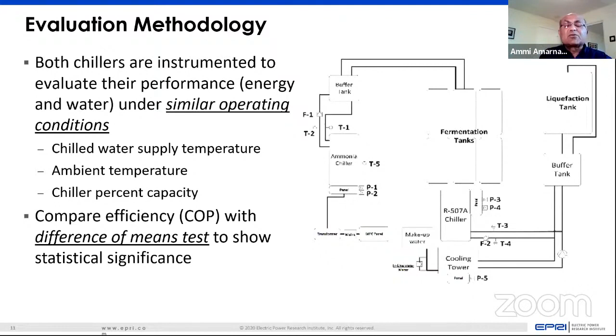The ambient temperature is low. Berkeley is near San Francisco and has very mild climatic conditions. So at operating conditions of 70 to 80% capacity and ambient temperature around 70 degrees Fahrenheit, the chiller is chilling the water down to 43 to 46 degrees Fahrenheit.